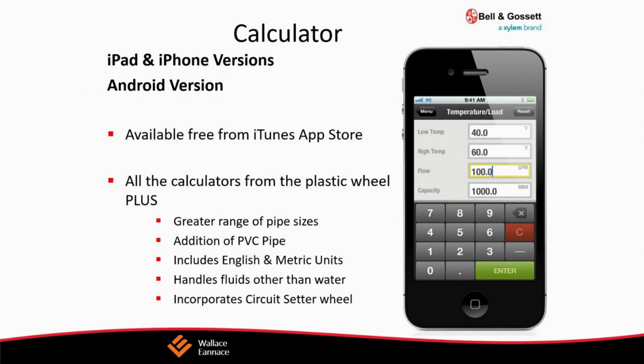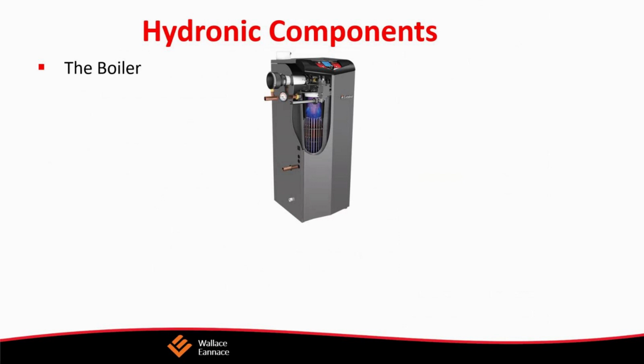So the rule of thumb for pipe sizing, when sizing the maximum flow rate that will fit through a pipe without making velocity noise, is that the pump head will be 4 feet for every 100 feet of piping. That's an important rule of thumb. So, piping capacities: if we have a 1/2-inch pipe, 4 feet of head per 100 feet will give us approximately 1.5 gallons a minute, which, once again, times 10,000, will give us 15,000 BTUs.